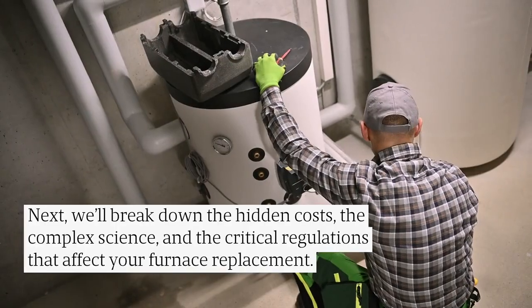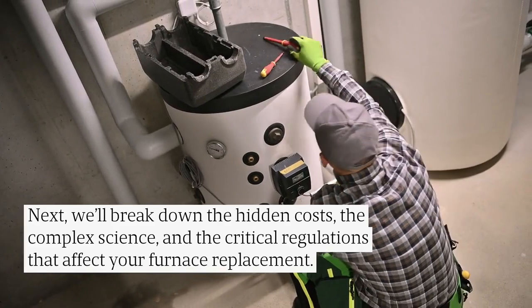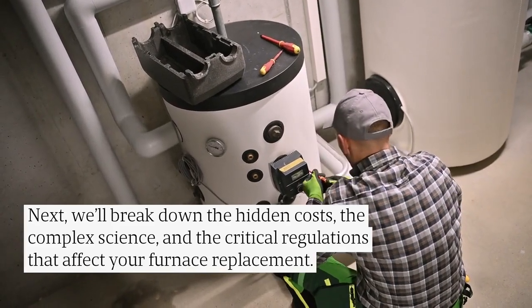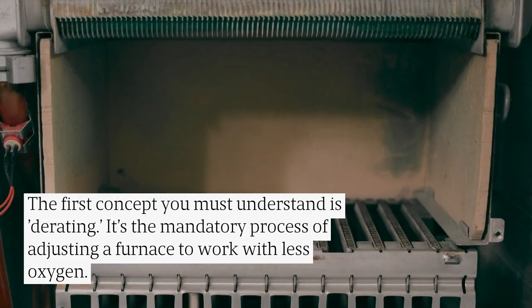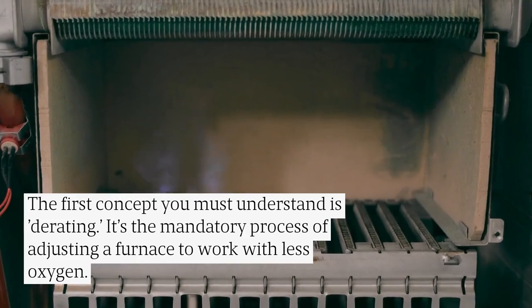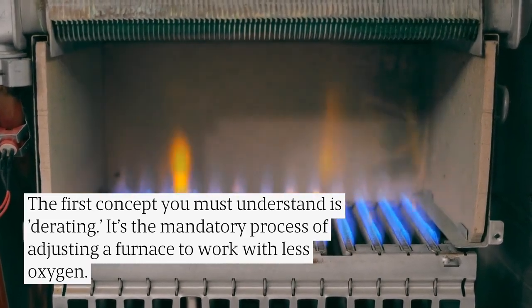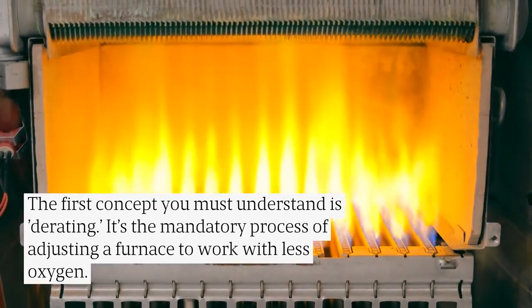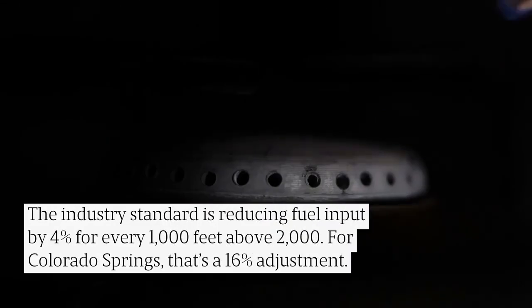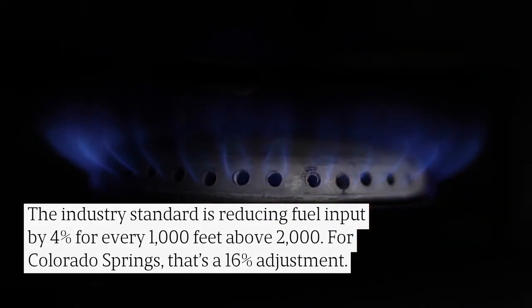Next, we'll break down the hidden costs, the complex science, and the critical regulations that affect your furnace replacement. The first concept you must understand is derating. It's the mandatory process of adjusting a furnace to work with less oxygen. The industry standard is reducing fuel input by 4% for every 1,000 feet above 2,000. For Colorado Springs, that's a 16% adjustment.